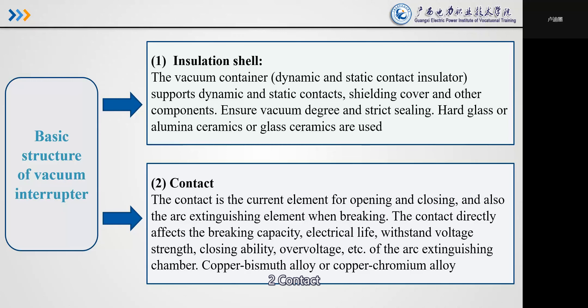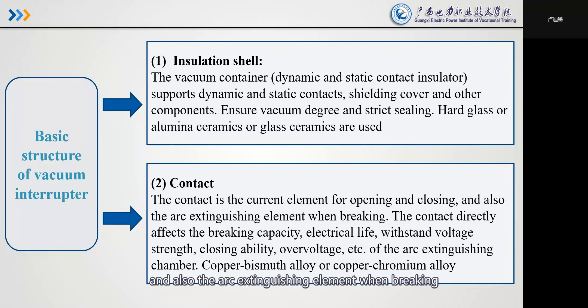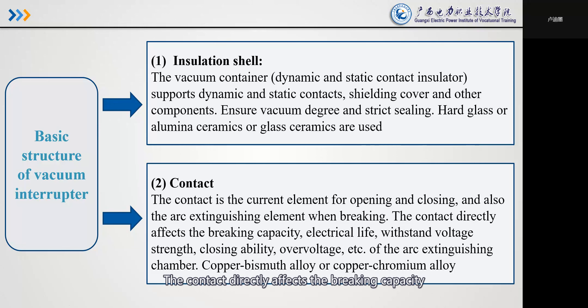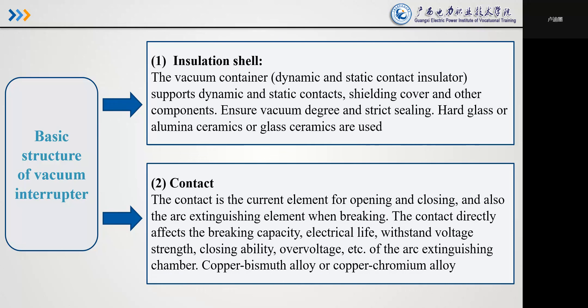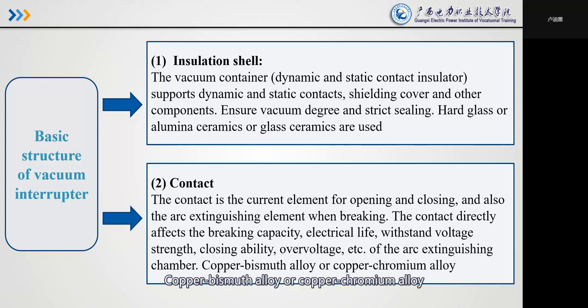(2) Contact: The contact is the current-carrying element for opening and closing and also the arc-extinguishing element when breaking. The contact directly affects the breaking capacity, electrical life, withstand voltage strength, closing ability, overvoltage, and so on of the arc-extinguishing chamber. Contact materials include copper-bismuth alloy or copper-chromium alloy.